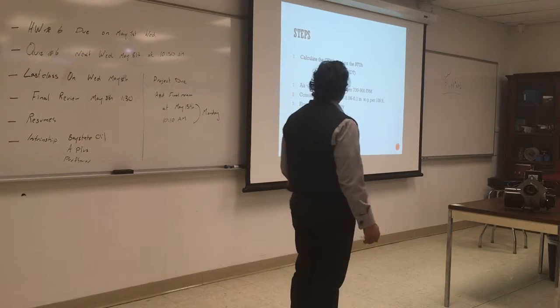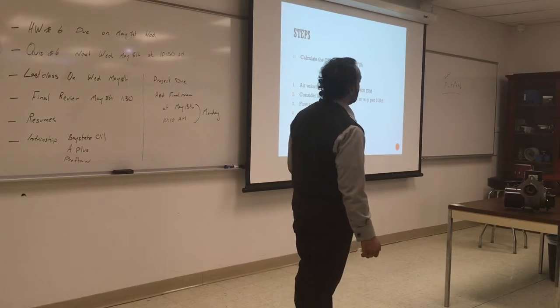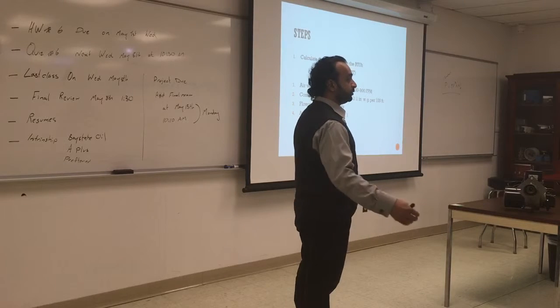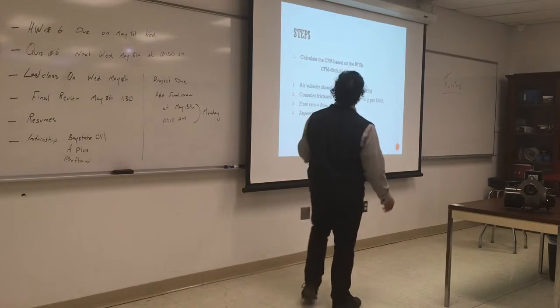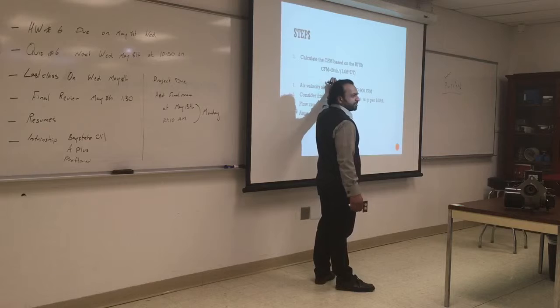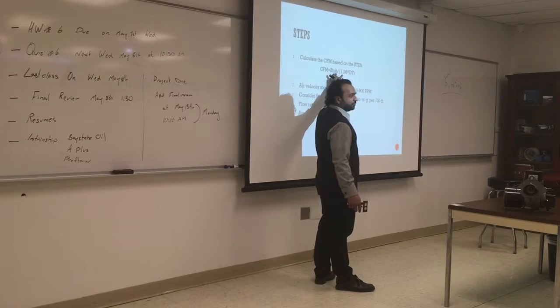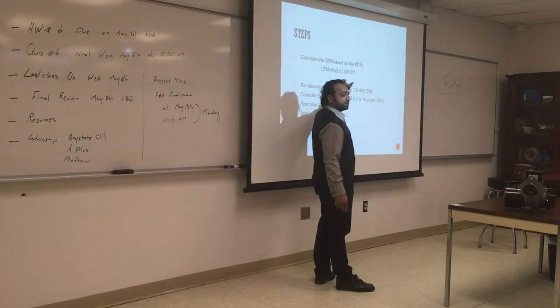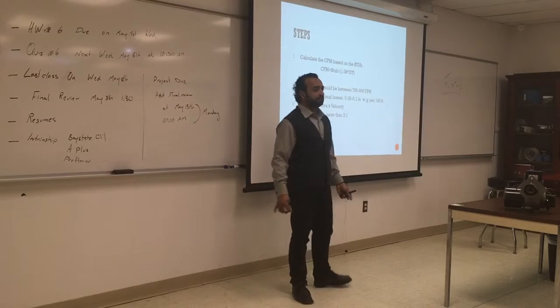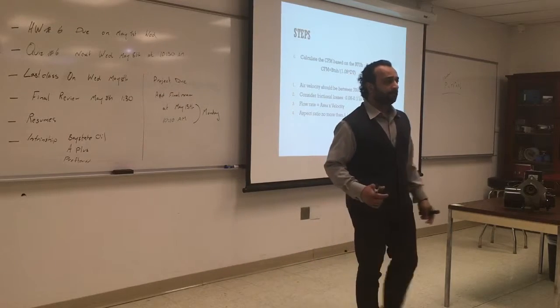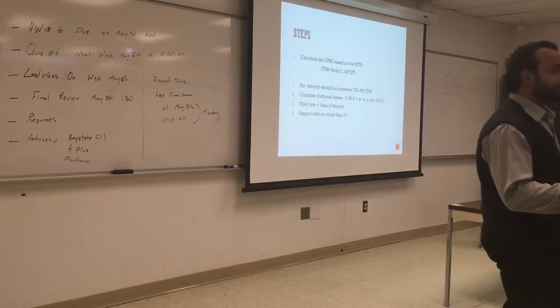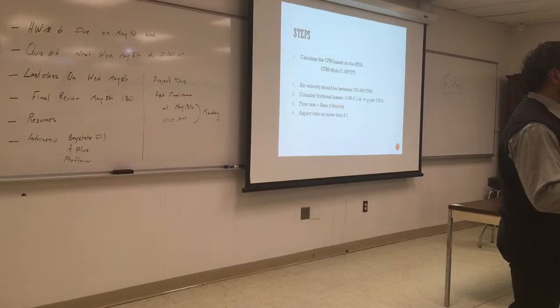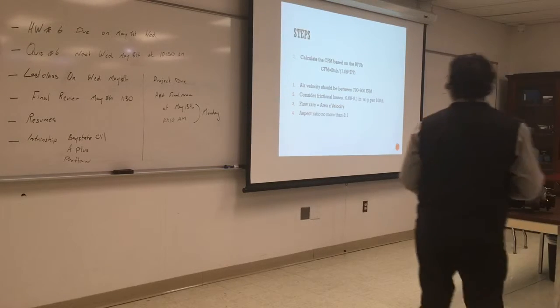So the first thing you want to do when you want to calculate the CFM, and that's something I want you to do for the project, once you do the cooling, I want you to give me the CFM, just to practice using this equation. It's the BTU of the room divided by 1.08, which is a constant, and delta T. Delta T is the supply temperature coming from the plenum, from the air handling unit, and the room temperature. I'll write this down.